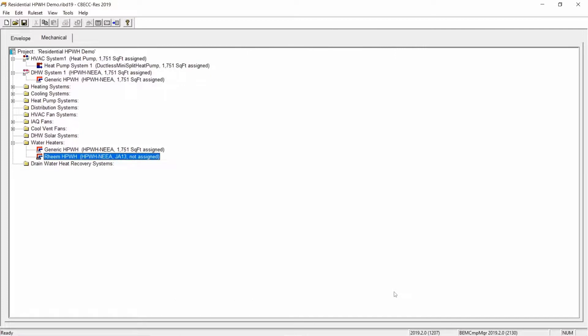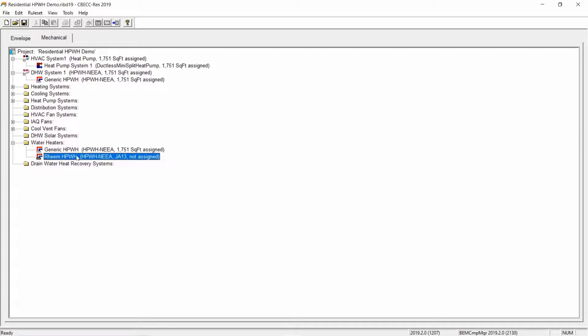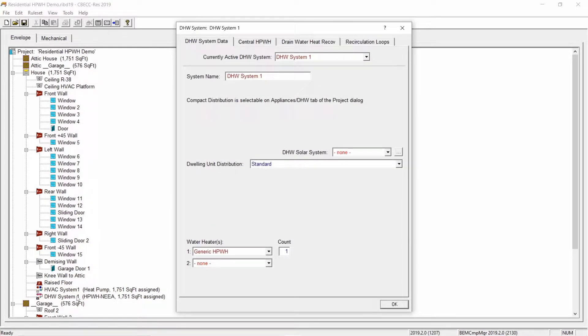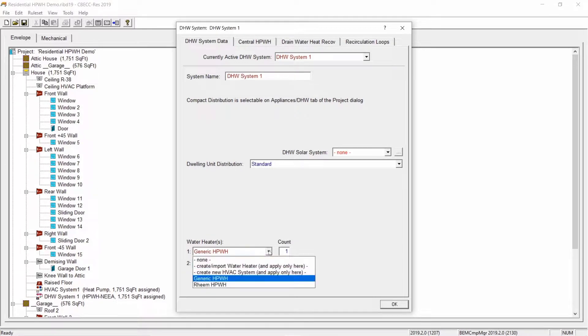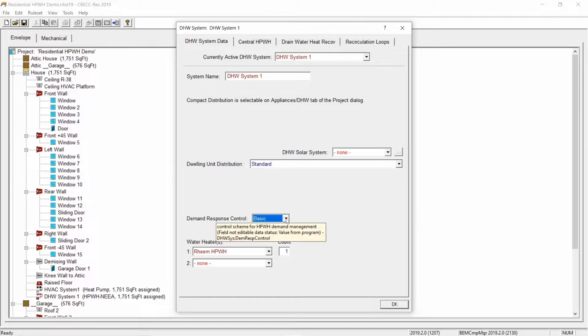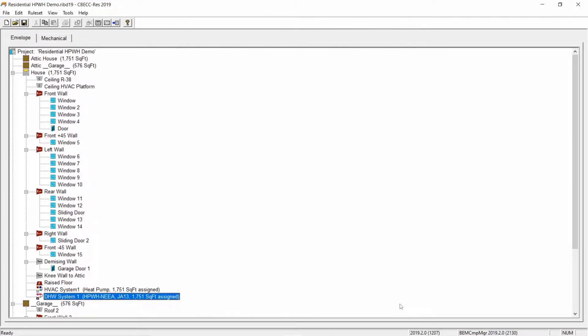You will notice that a second water heater is in the water heater folder. We will need to assign this water heater to the water heating system. Double click the DHW system component from either the mechanical or envelope tab to reopen the DHW system data dialog box. Then from the water heaters drop down, select Rheem HPWH from the list. When using a specified brand heat pump water heater, CBECC-Res sets the demand response control to BASIC, which is the only option for controls at this time. Now select the OK button and you've just created a specified brand heat pump water heater.